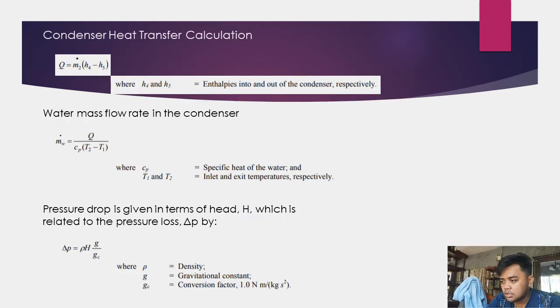Condenser heat transfer calculation. Q is equal to M sub 2 times H sub 4 minus H sub 5, where H sub 4 and H sub 5 are equal to the enthalpies into and out of the condenser respectively. Water mass flow rate in the condenser. Mass flow rate is equal to Q all over C sub P times T sub 2 minus T sub 1, where C sub P is equal to the specific heat of the water and T sub 1 and T sub 2 are the inlet and exit temperatures respectively.